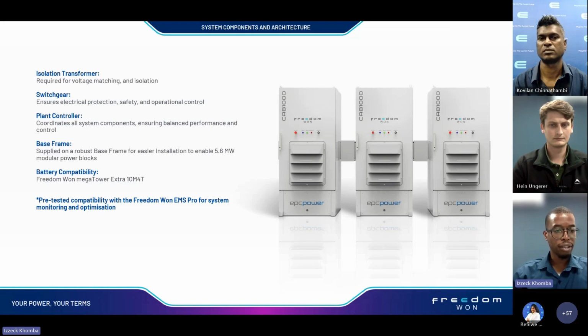Also, the switchgear is quite important, and it must be selected correctly for protection, safety, and operational control. This is quite critical, especially when you're using the inverter with UPS functionality protected bus to allow the seamless transition. We need to ensure that the switchgear is selected correctly, because the transition is also dependent on the type of switchgear that is integrated. The inverter requires a plant controller, basically to send and execute commands based on the system requirements, as the inverter requires an external plant controller to control.